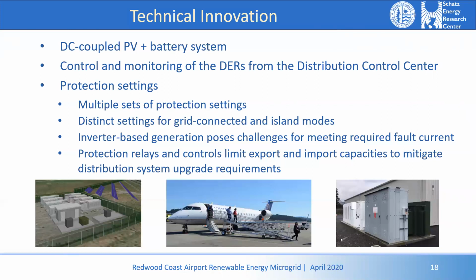It also provides some benefits in terms of control of the PV system, in terms of smoothing the output and minimizing spikes. Especially where we live, it's cloudy on the North Coast, and especially where the airport is, the weather can change very, very quickly. If it's cloudy and all of a sudden the sun pops out and you get a spike of power, that can cause problems. Certainly on an islanded grid, and even on a non-islanded grid when we're interconnected, because we have those export constraints, that will actually trip the breaker and put us in island mode, which we don't want to do unless there's a good reason to.